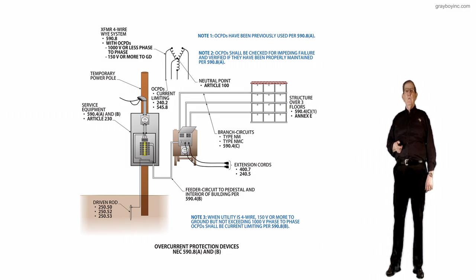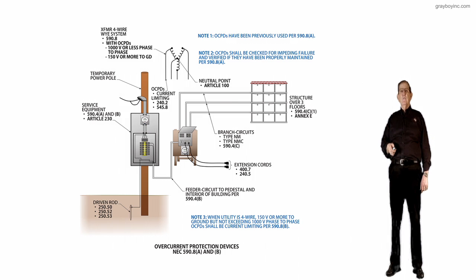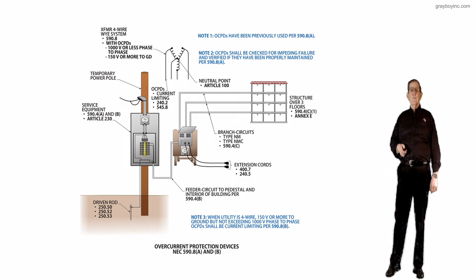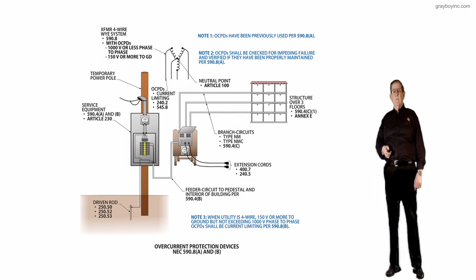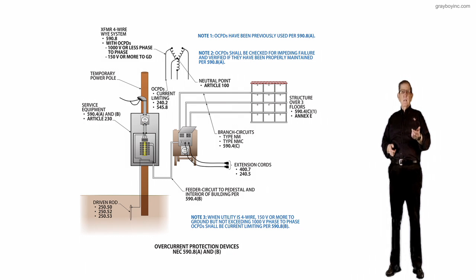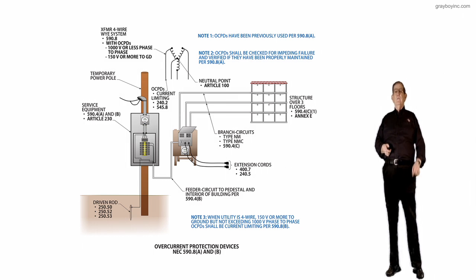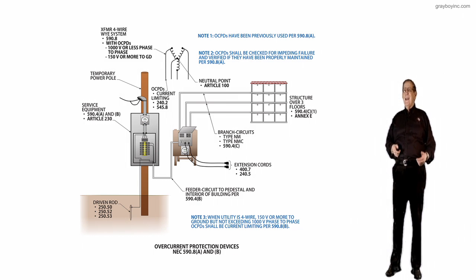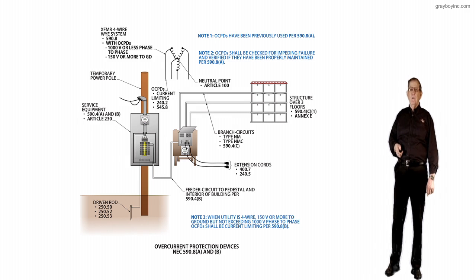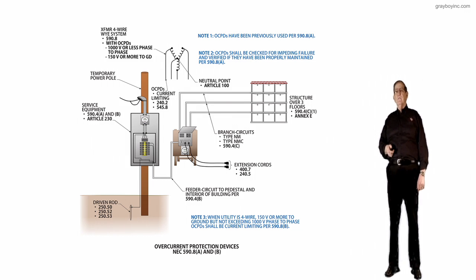Now let's review the driven rod, and you can see 250.50. We only have one rod, so that is our grounding electrode system. And then 250.52 says it's 8 foot in length, 8 foot into the ground. And 250.53 is what the electrician used to make that installation. So if you're going to have any of the rod above grade, you need to buy a 10-foot rod, because you need 8 foot in the ground. That's what's important here. And sometimes our electricians do not realize this. See, I'm not talking down to anybody. I'm just saying what we see out in the field.